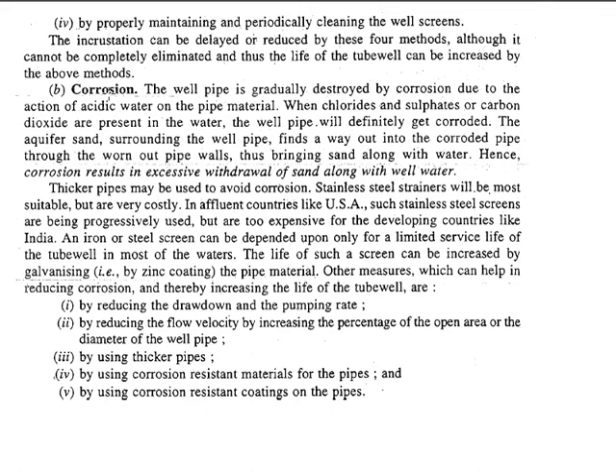The next cause of failure is the corrosion process. The well pipes used are prone to corrosion because they are exposed to acidic water, and when that comes in contact with metallic pipes, corrosion is a common process. Chlorides, sulfates, and carbon dioxide present in the water will cause the well pipes to corrode.